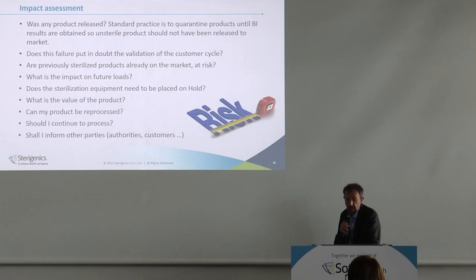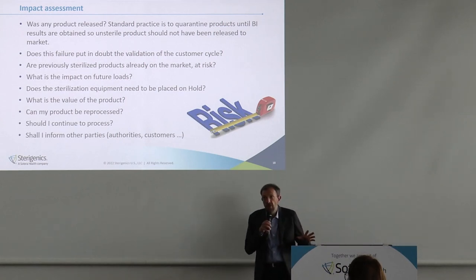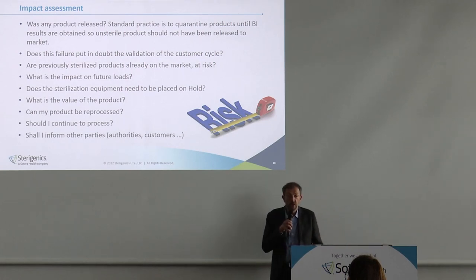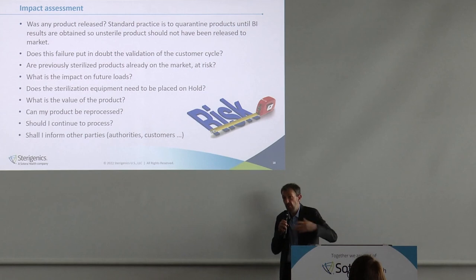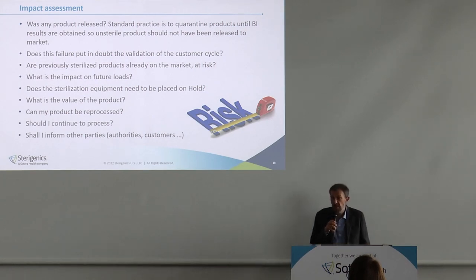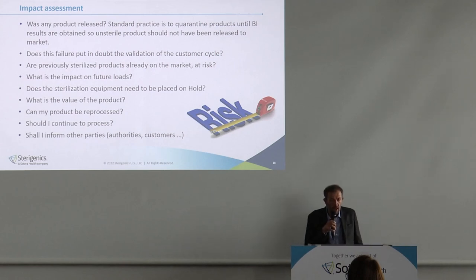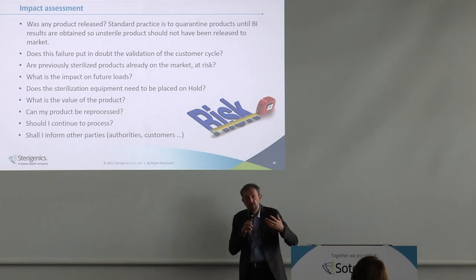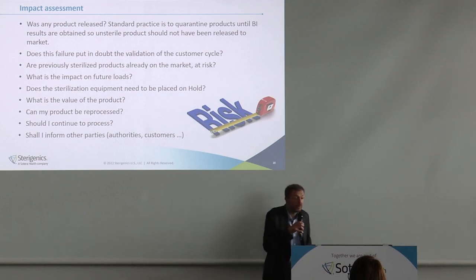In terms of impact, the load should be isolated. However, it may be that an urgent delivery has already gone to a hospital — in that case we need to ensure no product is being used on patients, and if it is, initiate a recall and perform a thorough analysis. Most of the time we can prevent this because the load will not be physically released until we have the certificate. We also need to check whether the failure could have an impact on the validation — can we question the validation, or were we just lucky, and is the cycle robust enough?